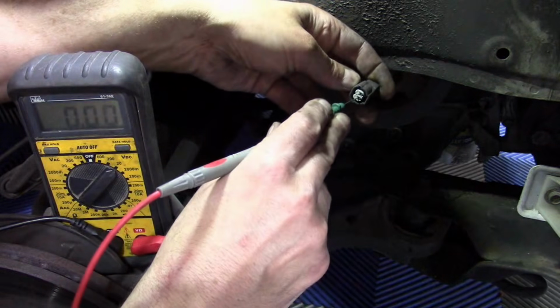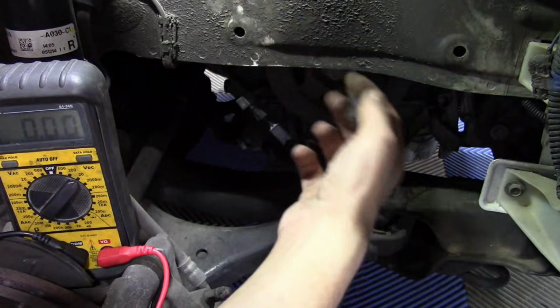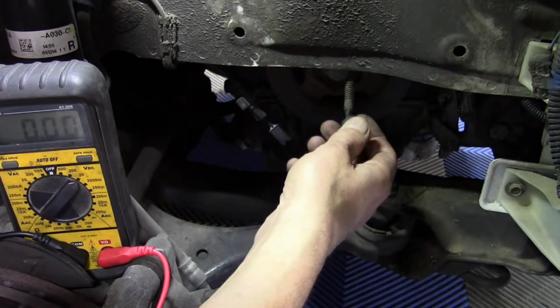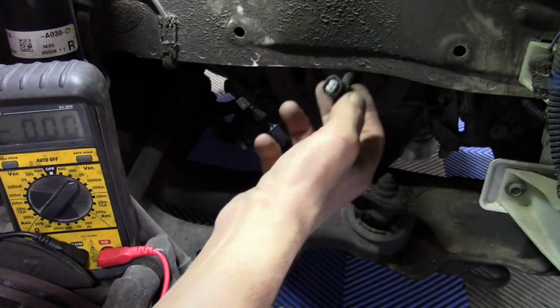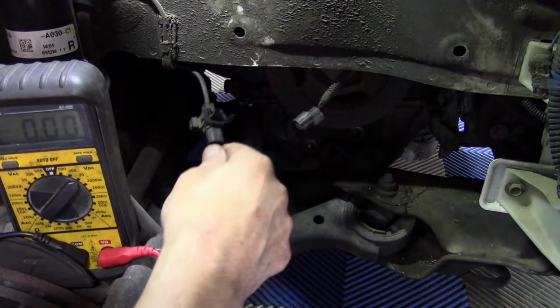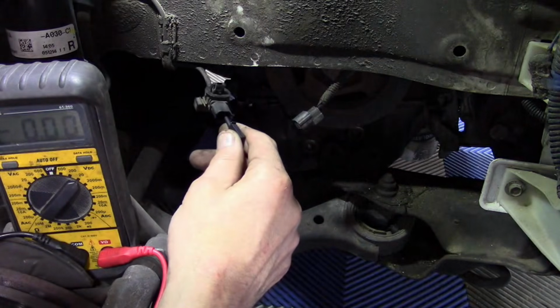Should be about 5 volts, and there it is. So that's a good indication that our wiring integrity to the module and the module itself are probably okay. Most likely this is going to be an issue with the sensor itself.